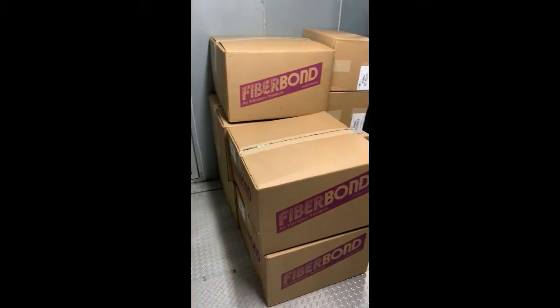They used to use the mini-pleat V-Style cells — got away from that. Those are packed one per box, they're bulky. Each unit takes 24 full-size filters and eight half-size, so that means we would have had to haul up over 30 boxes per unit. Instead, we cut that to a third.